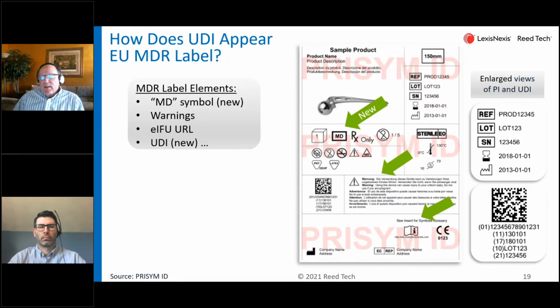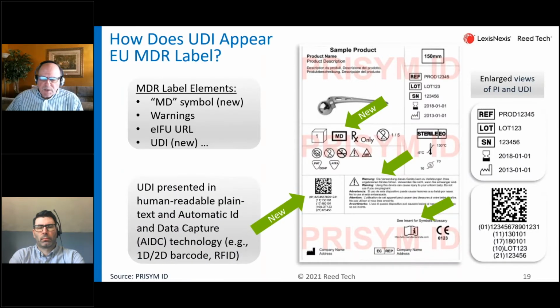How does UDI appear on the label? So there's a number of things that come into play, and we don't have time to dive into all of them, but at a minimum, the medical device symbol with MD in a rectangular box, warnings in various languages, and there's an increased use of the electronic information for use. For today's discussion, this is the example of how you would make use of a two-dimensional barcode and slide in the UDI into this particular label. And this could be a little bit of a problem with all these changes. You might have real estate issues, so keep that in mind.